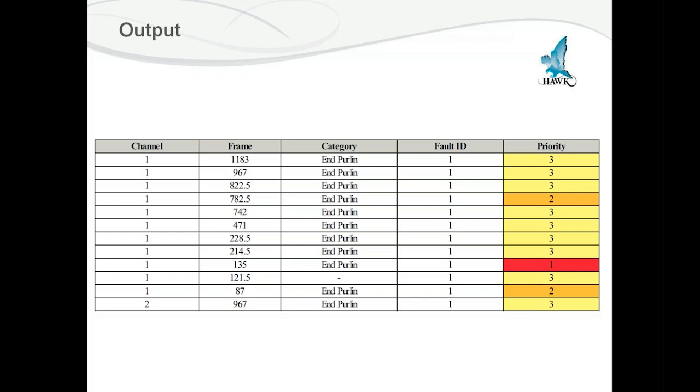Yes, so Shane has also asked, does the system alert based on the rate of change and not just the magnitude? Yes, there are two functions. There is, is it over this much? And there is also, how much has this increase accelerated? Is it accelerating or decelerating, the rate of increase? So we can actually look at that and go, wow, this has got real bad, real quick. We need to jump that priority up a little bit faster and probably go to an alert status earlier. It might not even be quite as strong as another failure, but it has progressed so quickly we don't want to leave it.